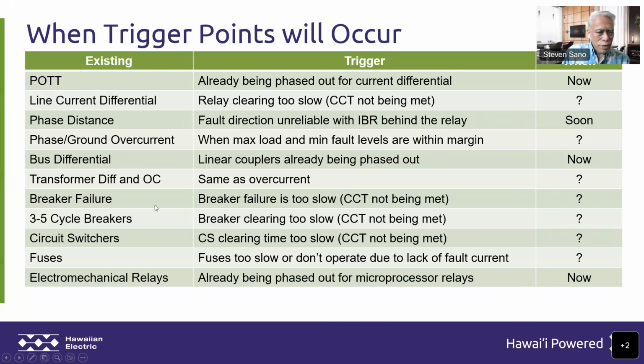The next three over here, breaker failure, going to faster circuit breakers, faster circuit switchers, again, all driven by critical clearing times for that. Fuses, fuses being too slow or not operating, but we have other opportunities to change out our fuses as well. Microprocessor relays, we have a process for that now, and again, just needs to be ongoing on that. So again, no crystal ball that will tell us when we need to do all of these things.